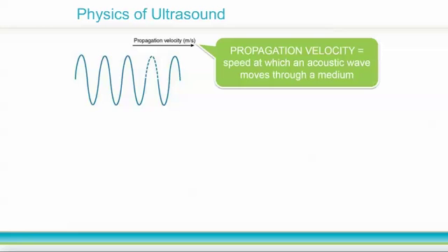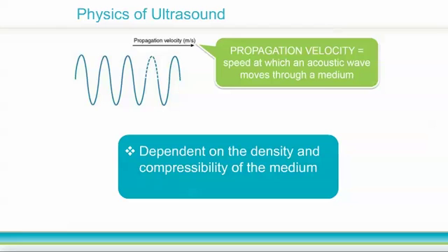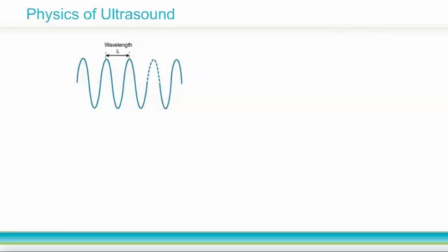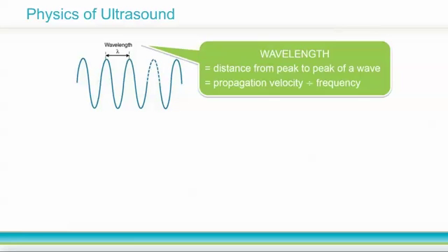Propagation velocity is the speed at which an acoustic wave moves through a medium. This is dependent on the density and compressibility of the medium, and determines acoustic impedance. We'll come back to that in a moment when we discuss tissue echogenicity. Wavelength is defined as the distance from peak to peak of a given wave. It is mathematically equal to the propagation velocity divided by frequency.